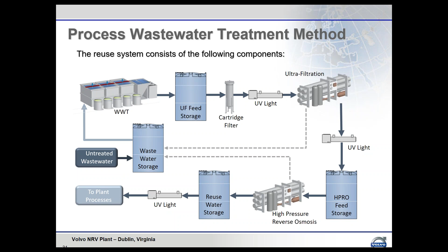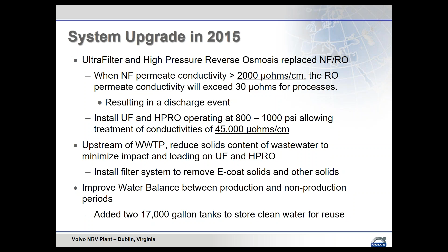For the system upgrade, overall, the upgrade improved the capability to meet the needs of the E-coat system by allowing treatment conductivities as listed above. We reduced the solids loading to the ultrafiltration and high-pressure RO system with additional pre-filter systems and added water storage to improve the water balance. Overall, the upgraded system could further reduce the discharge events to the POTW. Next slide, please.